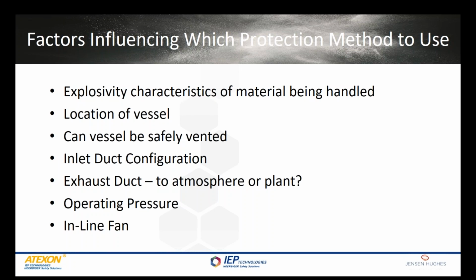The potential for there to be fire and/or explosion propagation through that duct during a deflagration or a conflagration event will have some effect on the type of protection needed. Certainly operating pressure has an effect. Even an inline fan, which can be an inline ignition source, will have some effect on the protection method that should be employed.